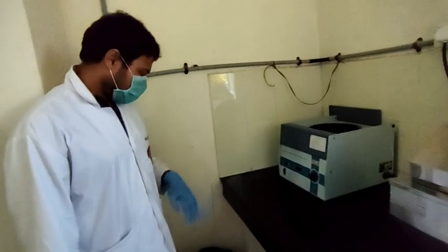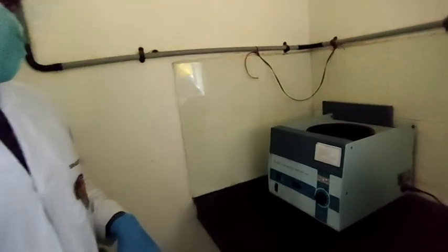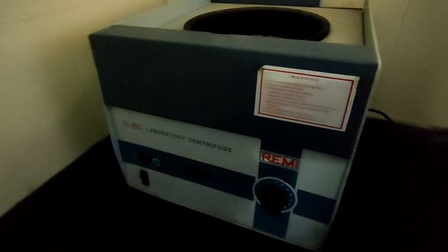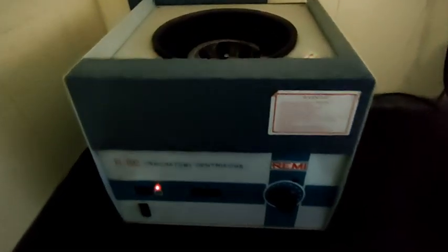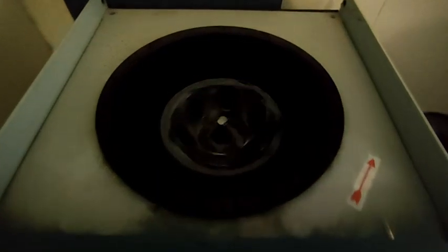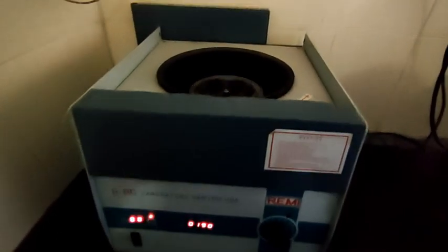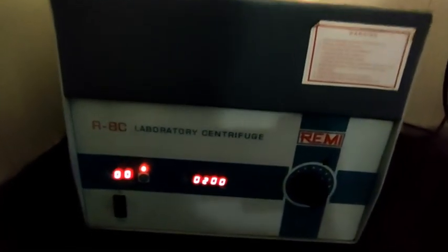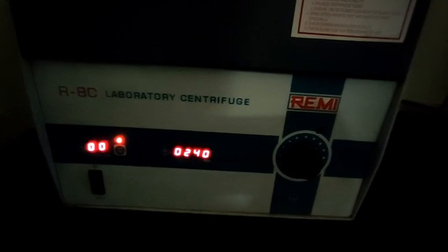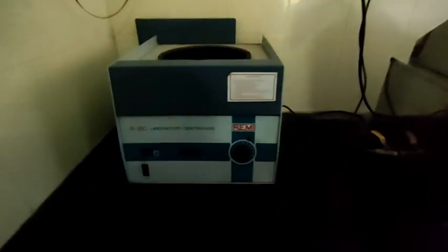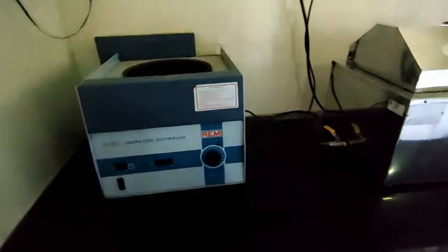Centrifuge. After turning on the start button, you can see the rotation of the rotor. The display is indicating the speed of rotation in RPM and the time of rotation in minutes. There is a manual setting available to change the speed and time of rotation. And lastly, it's always necessary to perfectly balance the weight before starting the instrument.